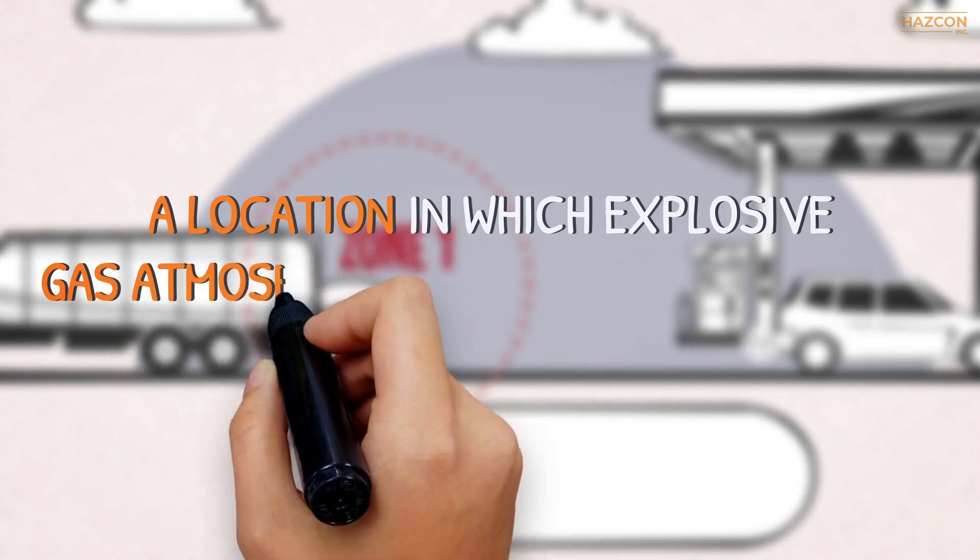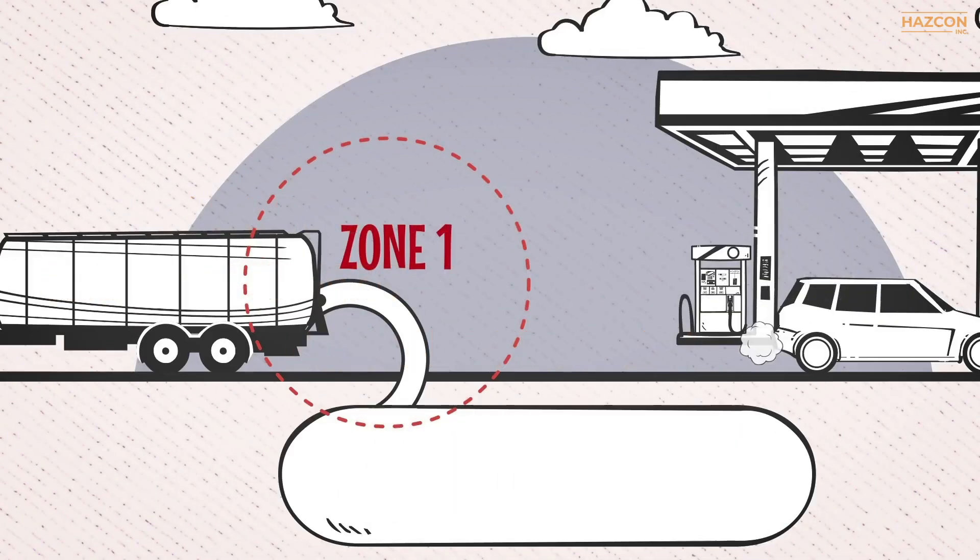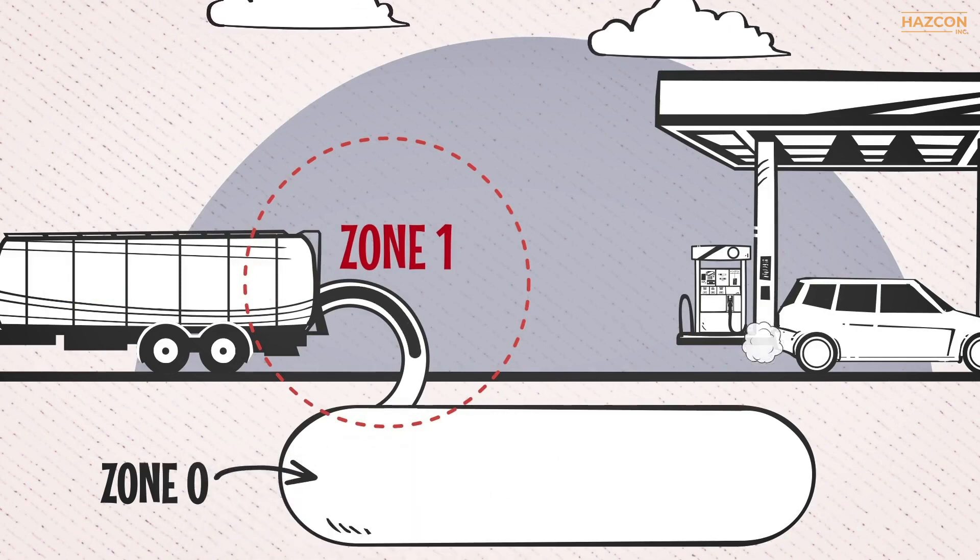Zone 1 is a location in which explosive gas atmospheres are likely to occur in normal operation, or the location is adjacent to a Zone 0 location from which explosive gas atmospheres could be communicated.